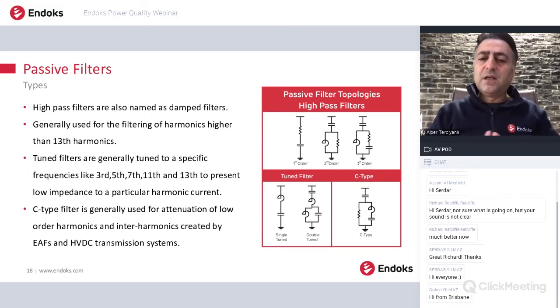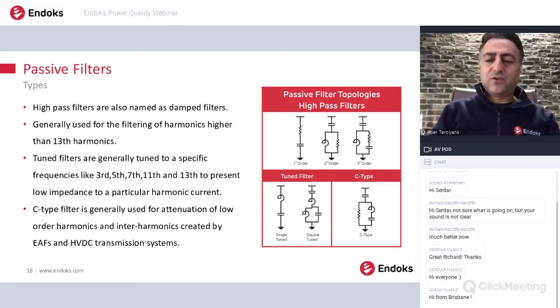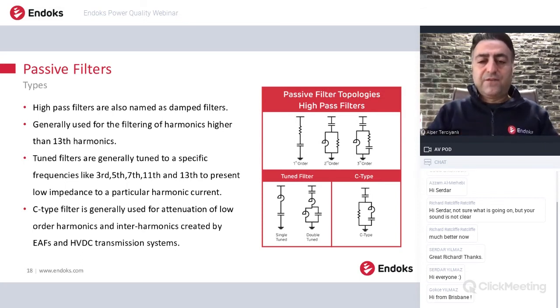And also the first order high pass filter, you see, with a resistor and a capacitor in series on the left hand side. We use these filters mostly because they are cheap compared to others and cost effective. And we use this filter, for example, not only for eliminating harmonics, but also for eliminating some transients because of switching. For example, switching a reactor, or switching a line, or in order to avoid traveling waveforms on the high voltage lines, we also use capacitors on the system with metal oxide varistors. So these are the filters we use for high frequency applications.